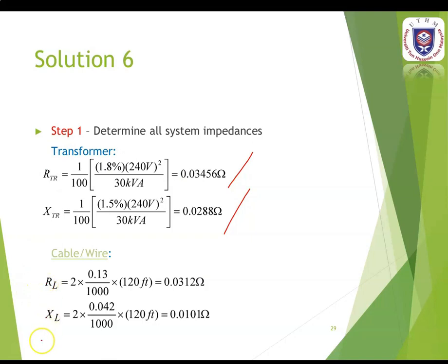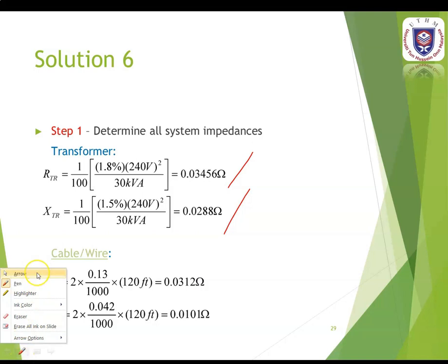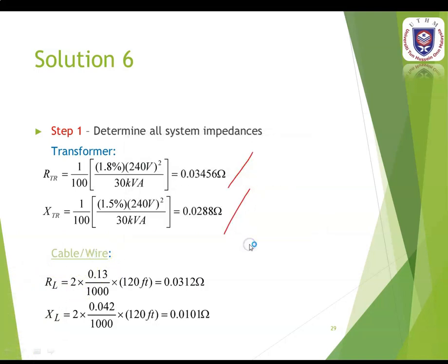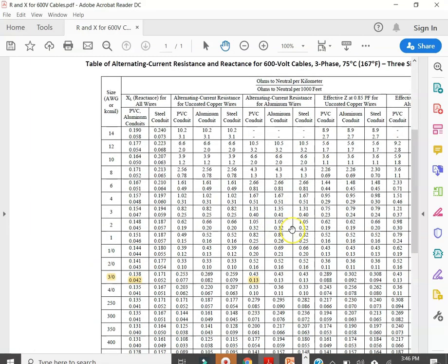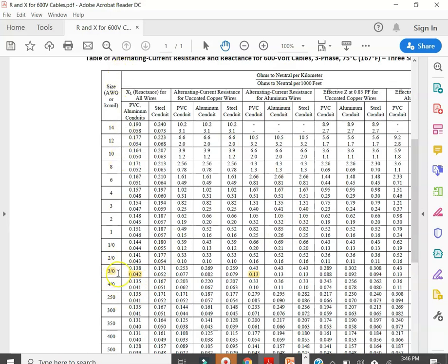Then you have to calculate the resistance and reactance for the cable or wire. You have to use the 600 voltage cable table. The size of the cable is 3/0. For alternating current resistance for aluminum wires, you choose the PVC conduit value which is 0.13 ohms per 1000 feet. For the reactance for wires, you look at the aluminum PVC conduit column which gives 0.042.